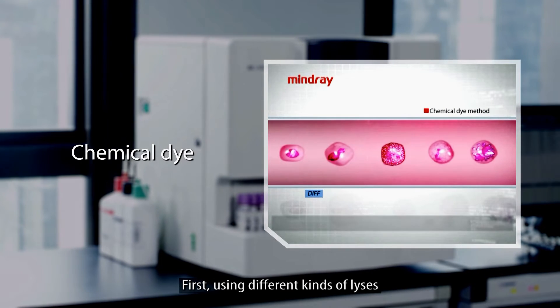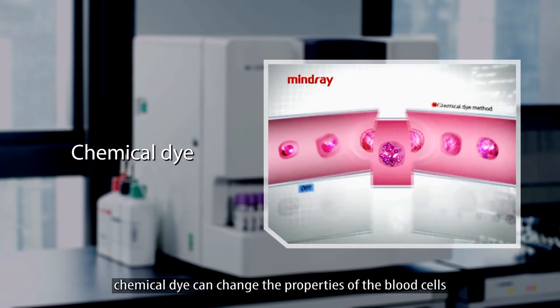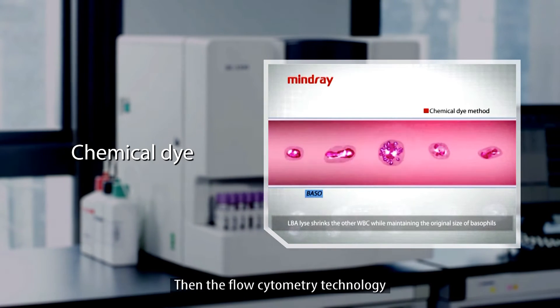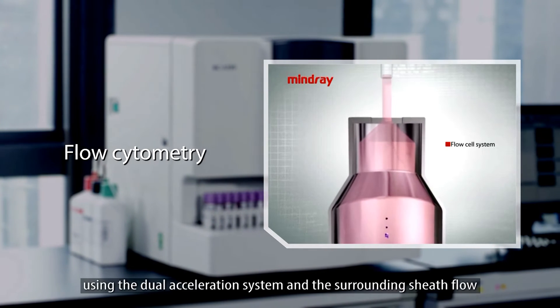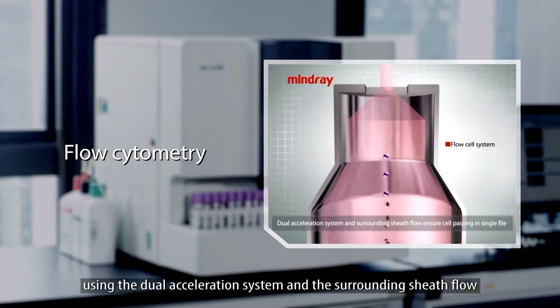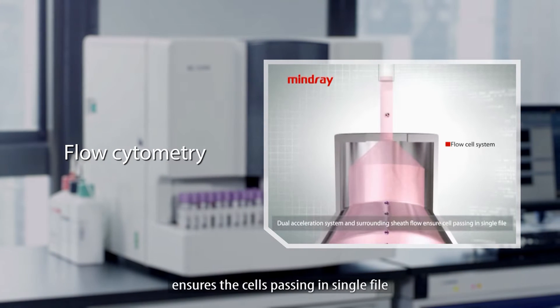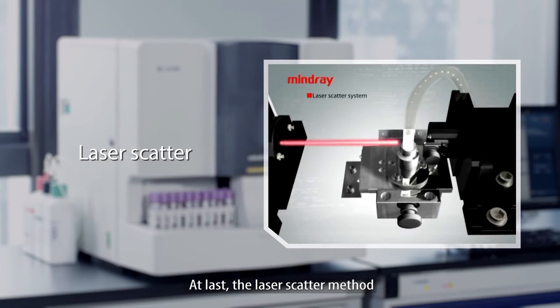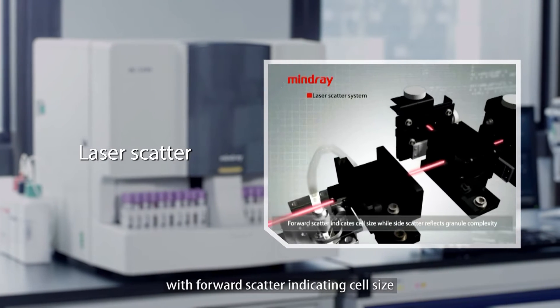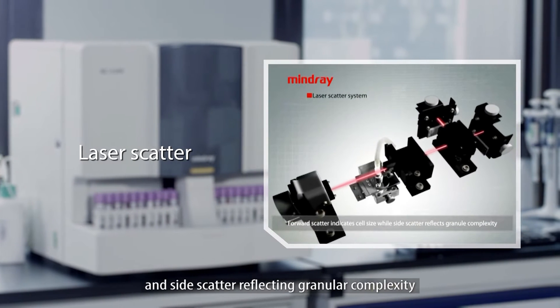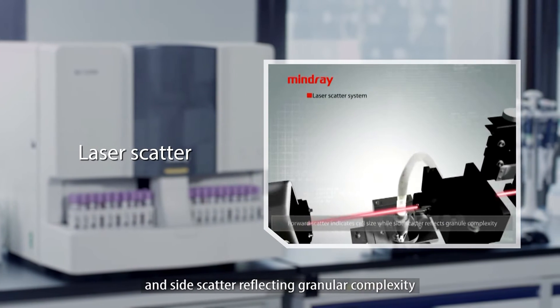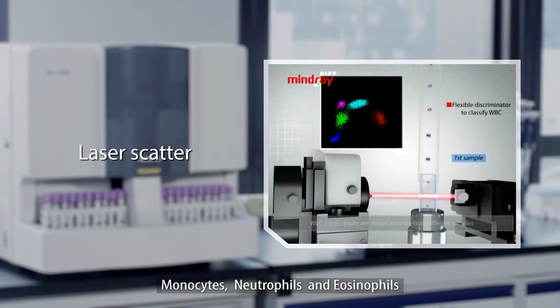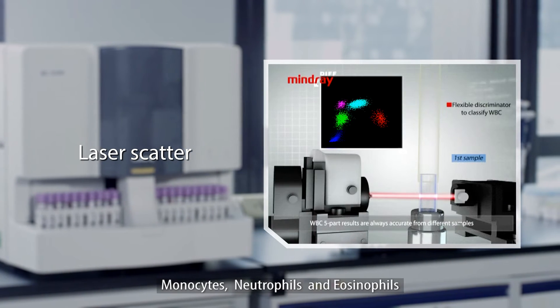First, using different kinds of lysis, chemical dye can change the properties of blood cells. Then, the flow cytometry technology, using the dual acceleration system and the surrounding sheath flow, ensures the cells passing in single file. At last, the laser scatter method, with forward scatter indicating cell size and side scatter reflecting granular complexity, can better differentiate lymphocytes, monocytes, neutrophils, and eosinophils.